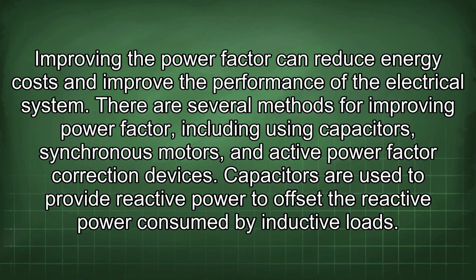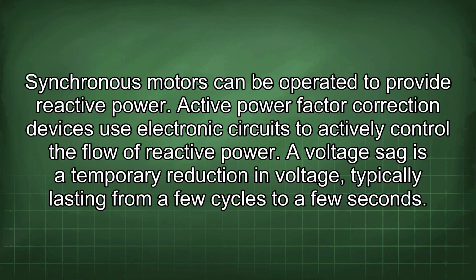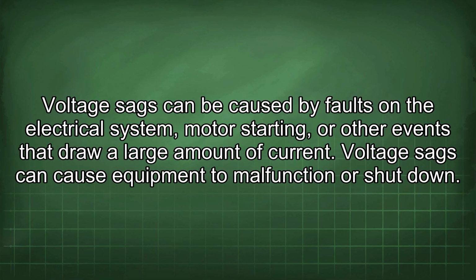There are several methods for improving power factor, including using capacitors, synchronous motors, and active power factor correction devices. Capacitors are used to provide reactive power to offset the reactive power consumed by inductive loads. Synchronous motors can be operated to provide reactive power. Active power factor correction devices use electronic circuits to actively control the flow of reactive power. A voltage sag is a temporary reduction in voltage, typically lasting from a few cycles to a few seconds. Voltage sags can be caused by faults in the electrical system, motor starting, or other events that draw a large amount of current. Voltage sags can cause equipment to malfunction or shut down.